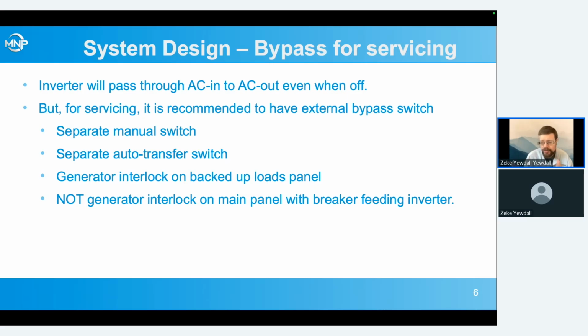You want to make sure that it doesn't connect the two together, because that will confuse and possibly damage the inverter. Most of those are designed to not do that, because you don't want to do that with the grid and a generator either. You want to verify that.